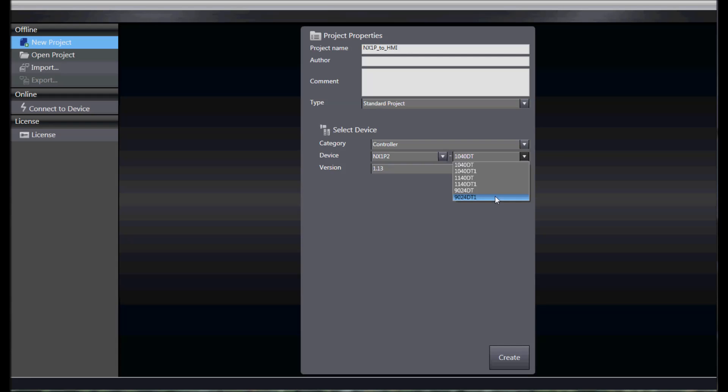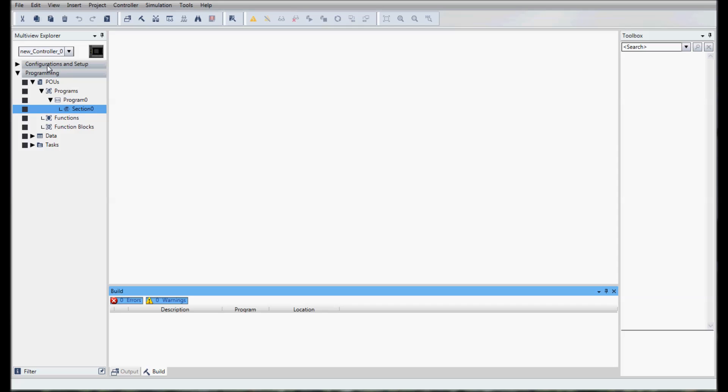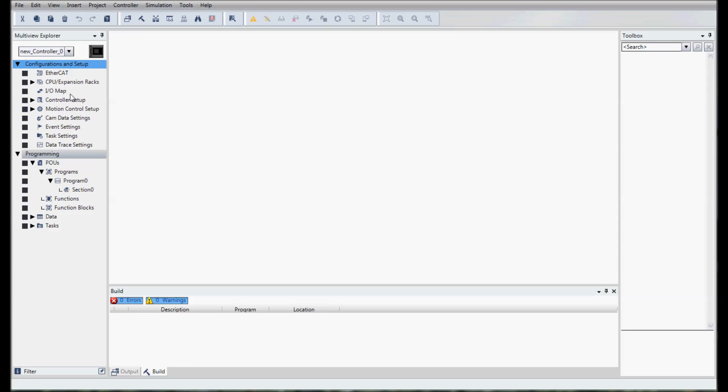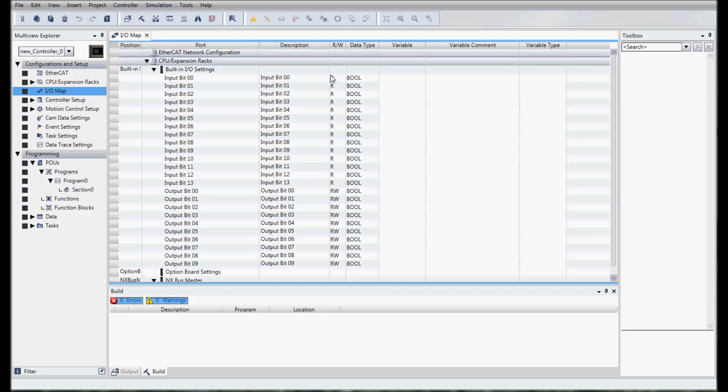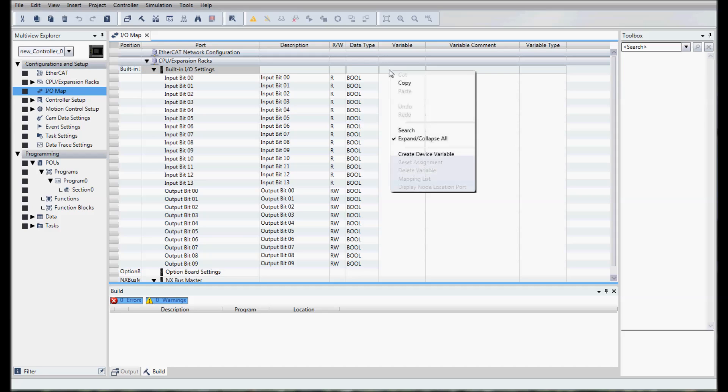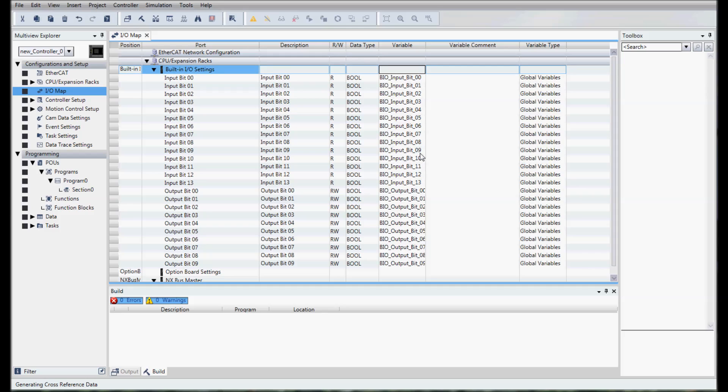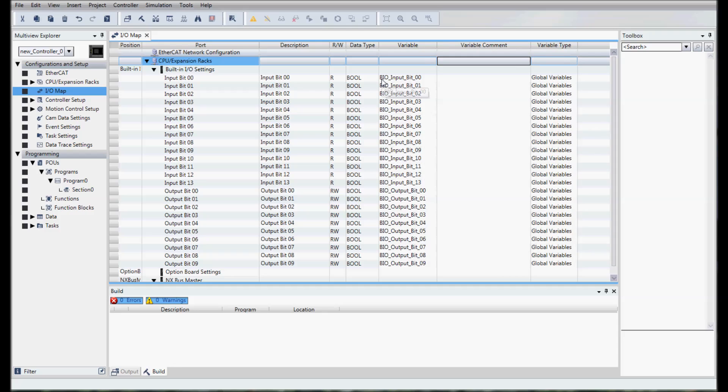It's a 24 point I/O unit with PNP outputs. In this case it's version 1.13. We'll hit create and the first thing that we're going to do is go to our I/O map where all the inputs and outputs are. We're going to create some device variables. We'll right mouse click and select create device variable and it auto named our device variables: Bit I/O input bit 0 up to 13 and Bit I/O output bit 0 to 9.